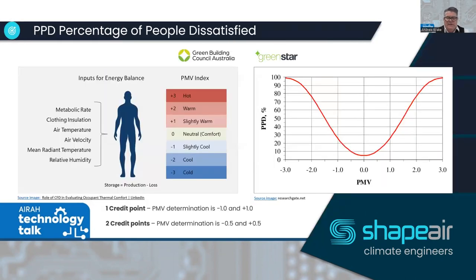This reaction to temperature and velocity was developed by Professor Fanger in Denmark, who studied people's reaction to temperature and velocity and their combination to create a predictable value — the Predicted Mean Vote (PMV) index. This shows a neutral point with a scale of plus one to plus three (hot) and minus one to minus three (cold).